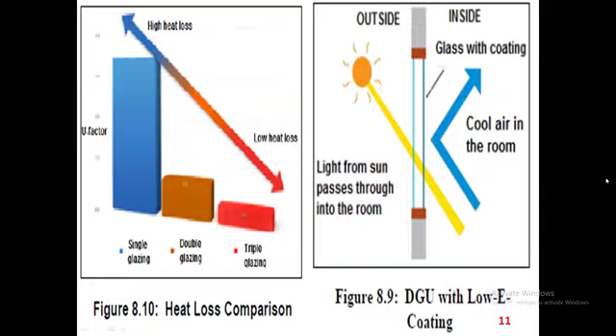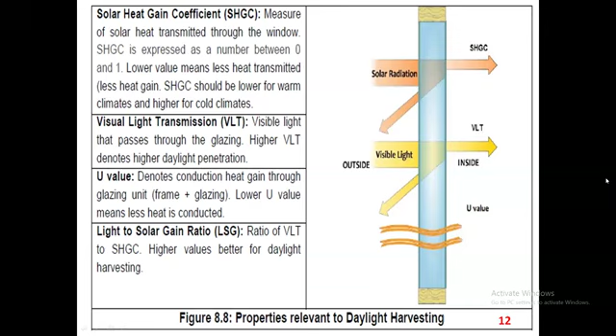See, for an EEE department, why I am talking about the thermal side of industries and buildings is because the thermal side of the building decides the energy consumption of the given building. The solar heat ingress for the given building is very much more, so definitely that needs to be controlled. This is where the visible light and the solar radiation matter, and how this relates to the U value. Ultimately the U value denotes the conduction of heat gain through the glazing unit. The lower the U value, automatically it is better for us.